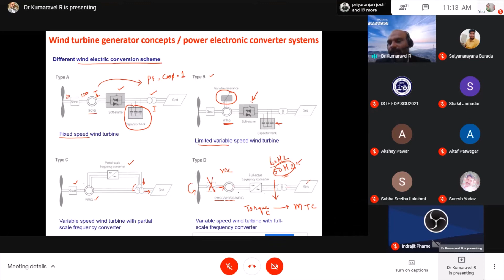So you have to have strong monitoring systems. You have to monitor the RPM, the current and voltage coming out from the generator, and what the demand is, how much power the utility board wants. Keeping all this in mind, the controller takes a decision and accordingly harvests the available torque coming in the input shaft of the generator. That is called the torque controller. There is a torque controller connected to the main turbine controller, which monitors how much torque is available in the input shaft, and how much power it can harvest.